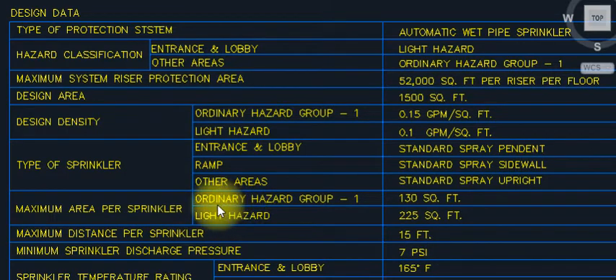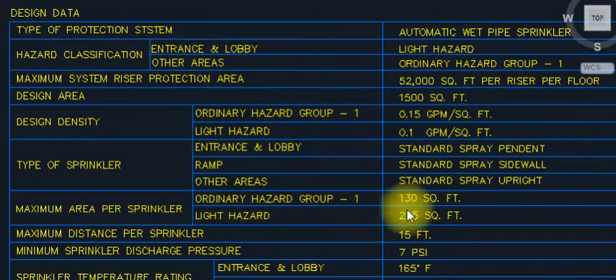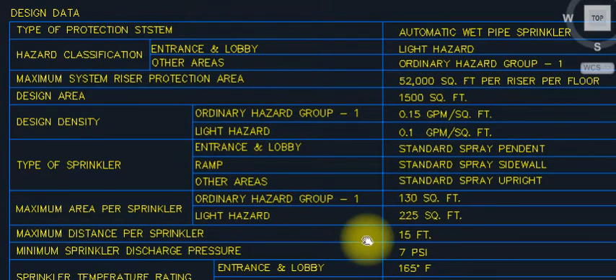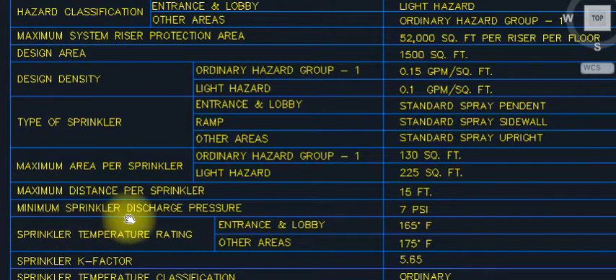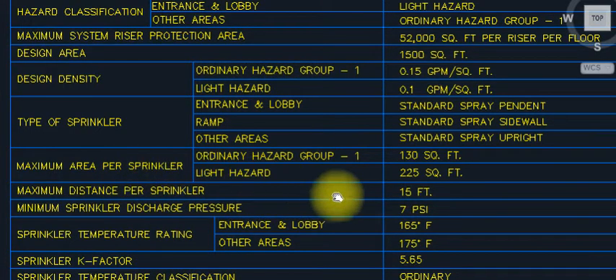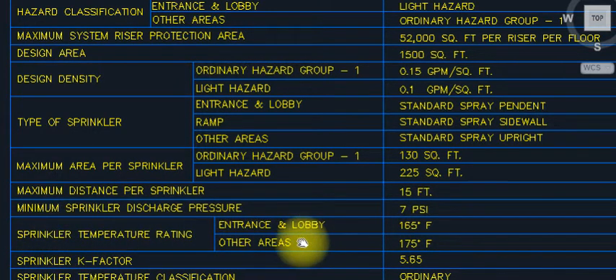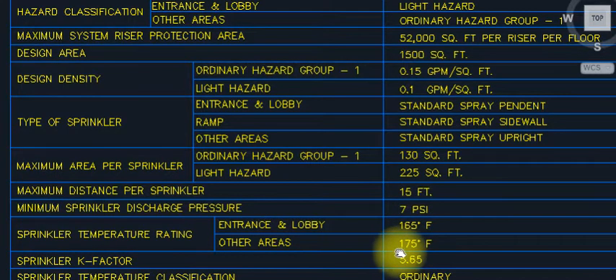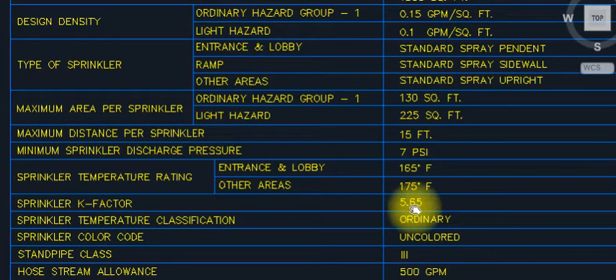Maximum area per sprinkler: ordinary hazard group 1 — 130 square feet; light hazard — 225 square feet. Maximum distance between sprinklers: 15 feet. Minimum sprinkler discharge pressure: 7 PSI. Sprinkler temperature rating: entrance lobby — 165°F; other areas — 175°F. Sprinkler K-factor: 5.65.